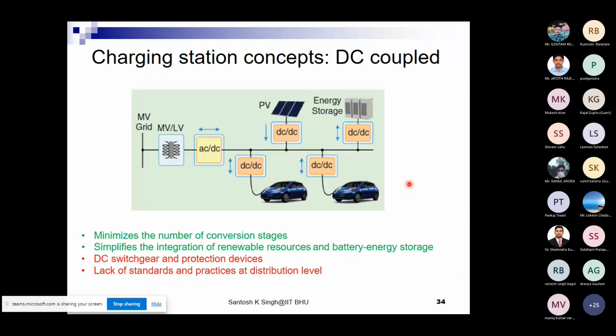Likewise, we have a DC coupled system where instead of an AC coupling, we can put a bigger rectifier in the first stage, and then have everything in the form of DC. This looks comparatively better than the AC coupled system, because if you have an 800 volt DC line, you can take everything without DC to AC or AC to DC conversion. That is done centrally at one place, and throughout this architecture it is a stiff DC.